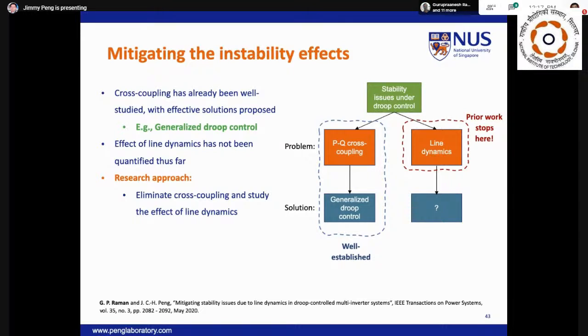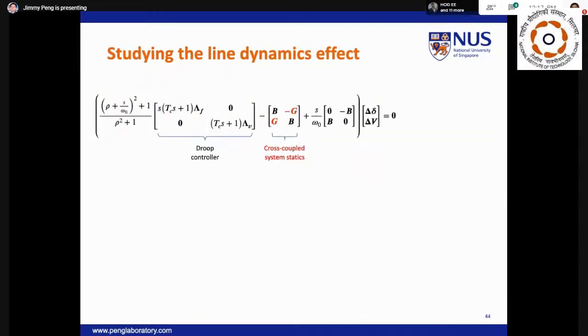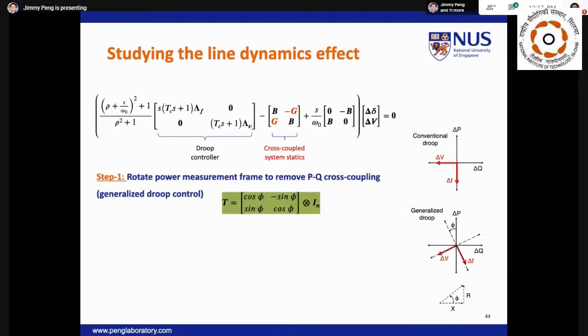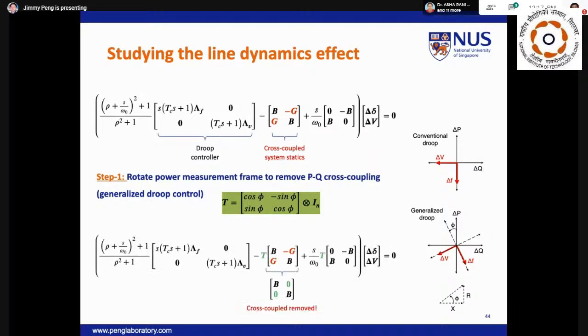any R by X ratios. We will return to the small signal model of the multi-inverter system shown here. The first step is to rotate the power measurement frame to eliminate the cross-coupling, as proposed by the generalized Droop control. The angle of rotation, phi, is governed by the R by X ratio of the system. The resulting transformation matrix is denoted as T, where I_N is the identity matrix of size n, and n refers to the number of grid-forming inverters.